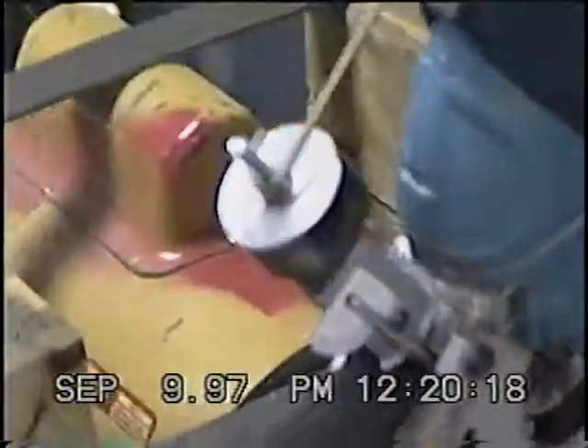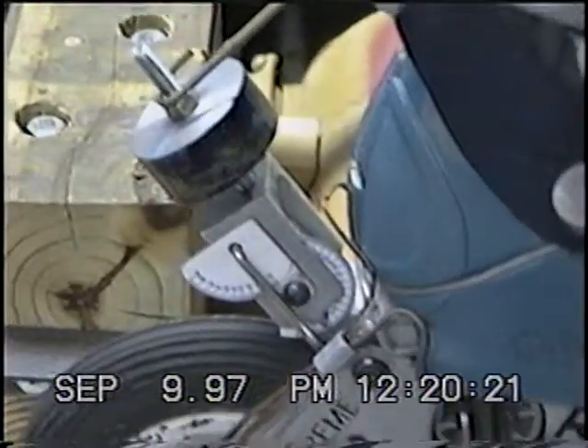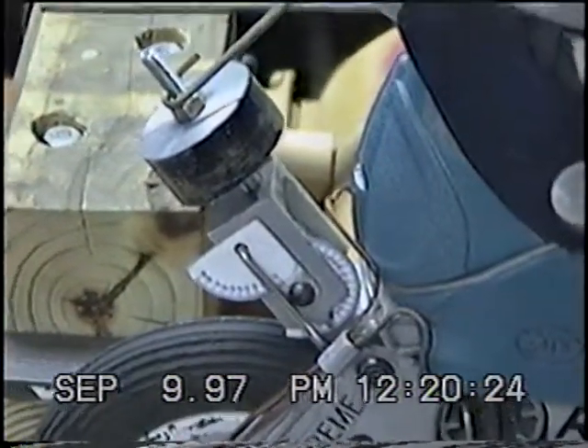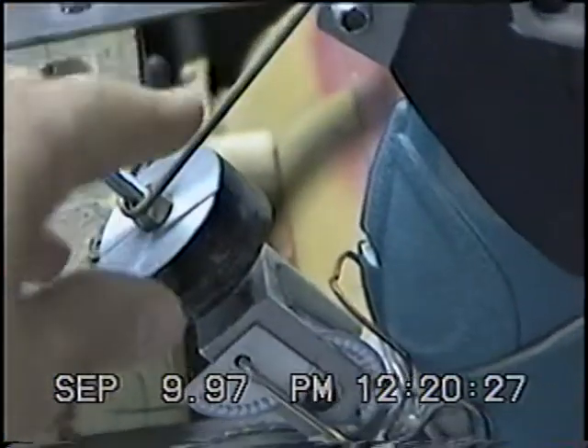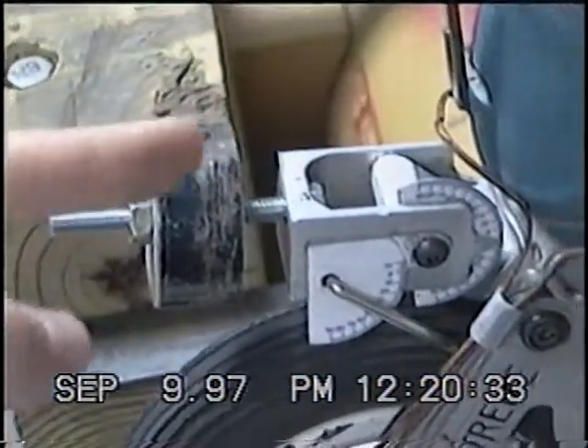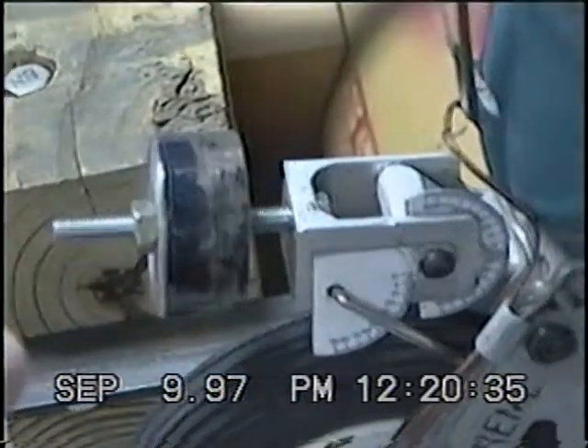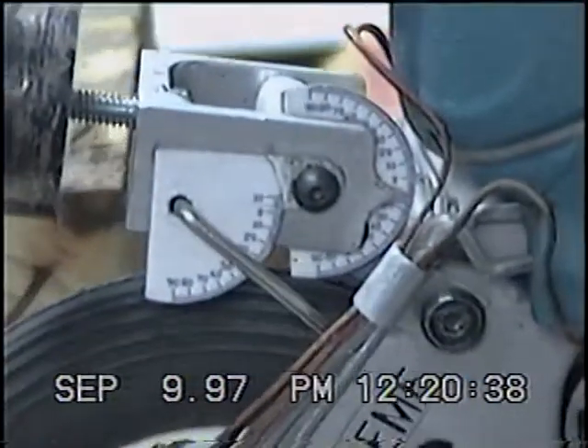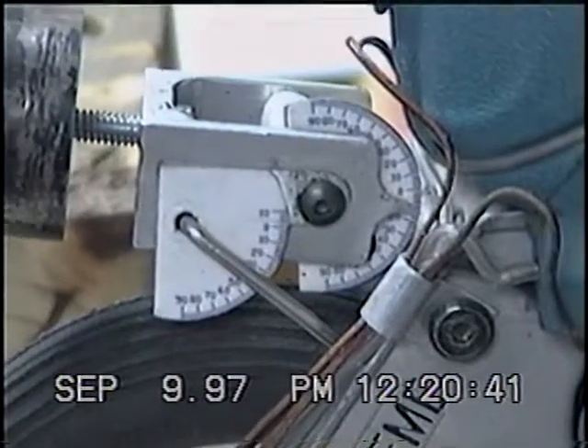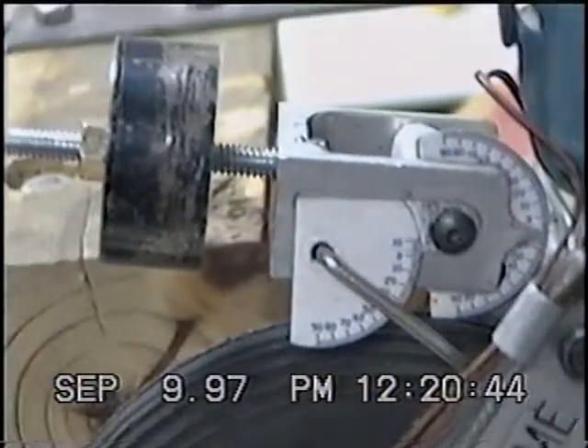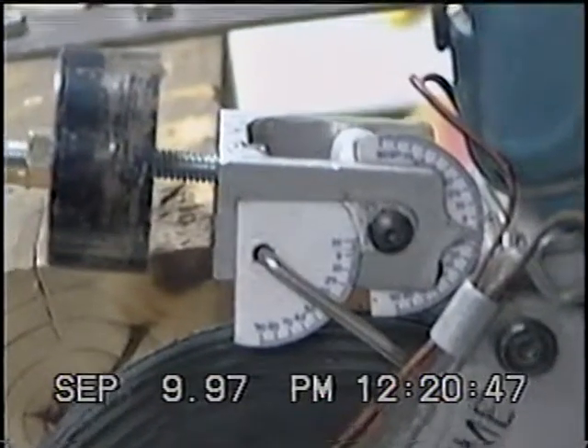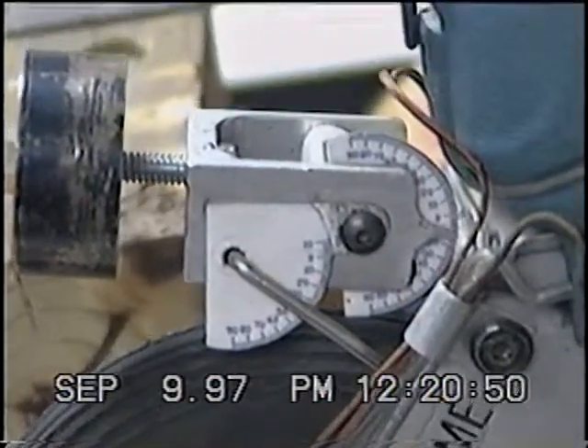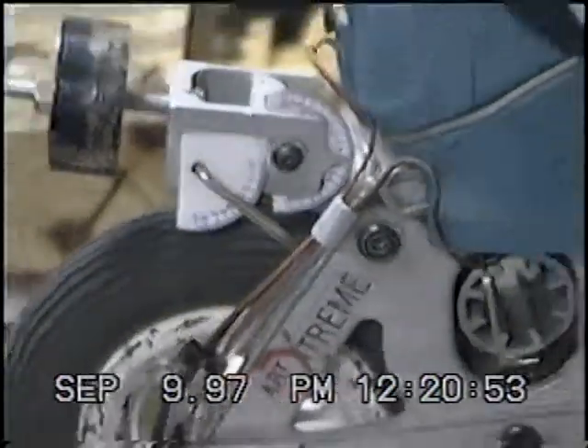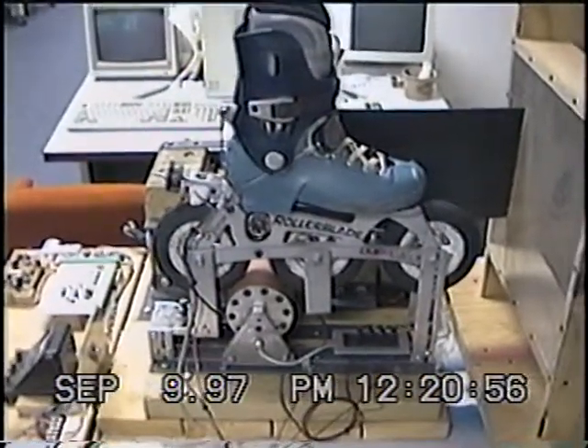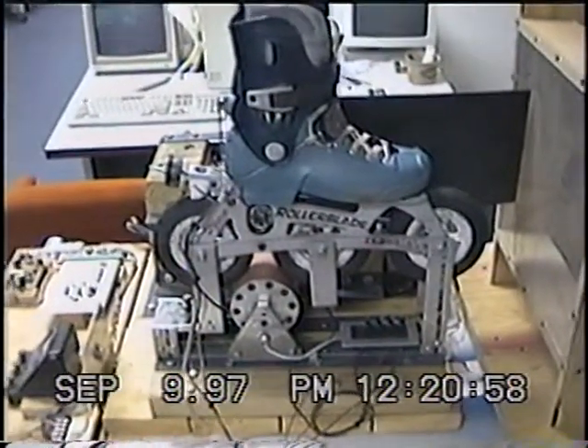and one more item is we have the weight set up on the actuation mechanism so that the weight can be turned in and out to increase or decrease the amount of braking force that's applied. We also have 2 dials here which allow us to determine what the angles of the main actuating mechanism and also the wire forms are, and that way we can determine what the actual braking force is. So I'll back out here and get the data acquisition ready to go, and then we will start up and do a test run.